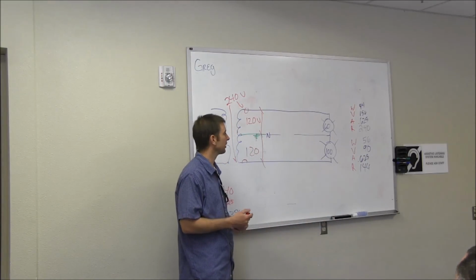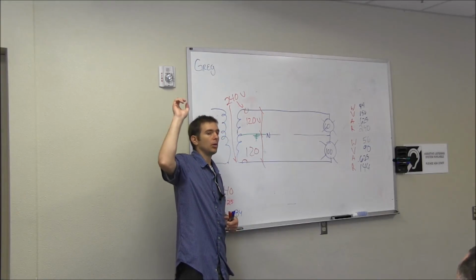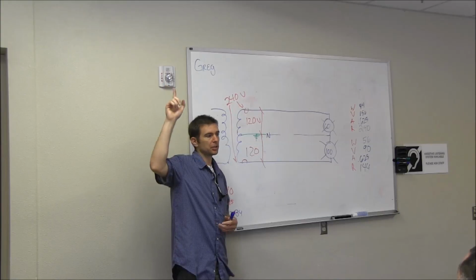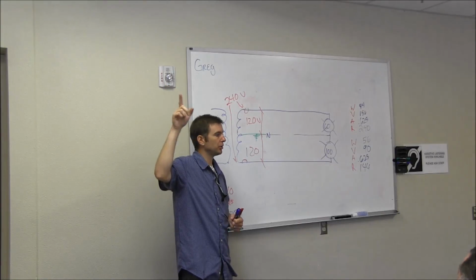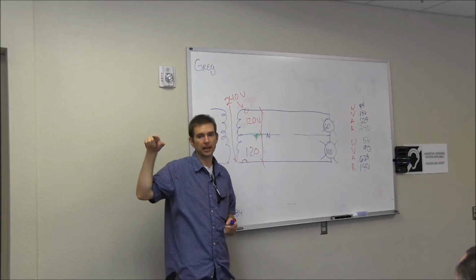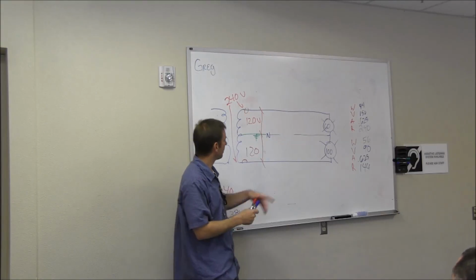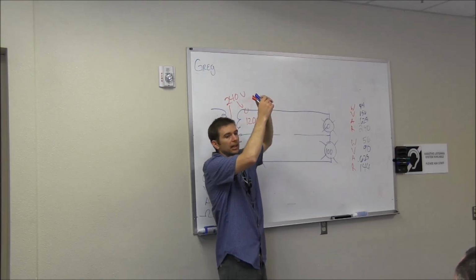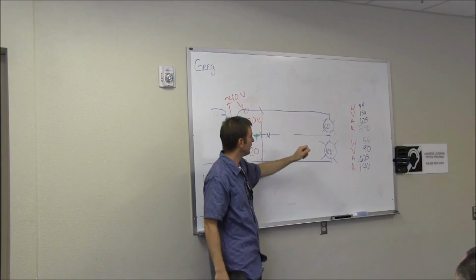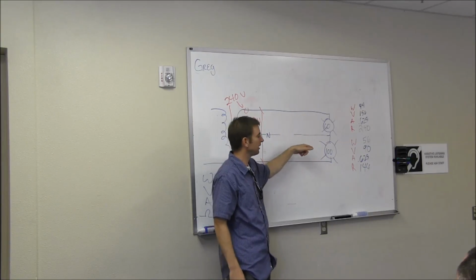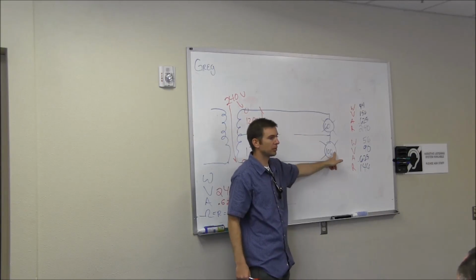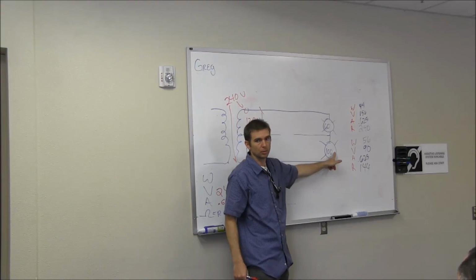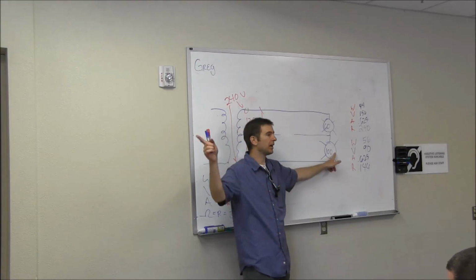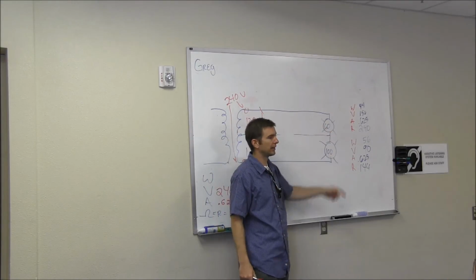What happened is, for a long time, people were changing out old light fixtures, the T12s with magnetic ballasts, to new light fixtures with electronic ballasts. They would have multi-wire branch circuits, and in replacing a light fixture, they would open up that neutral and do exactly the same thing. The magnetic ballasts, which were the higher wattages, would not get burned up, but the electronic ballasts would fry.